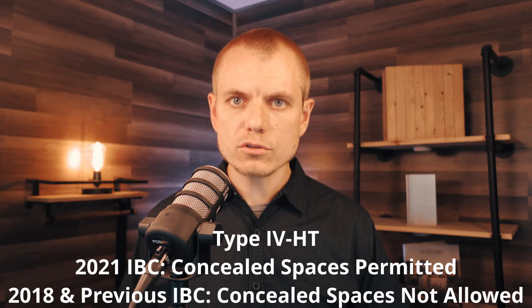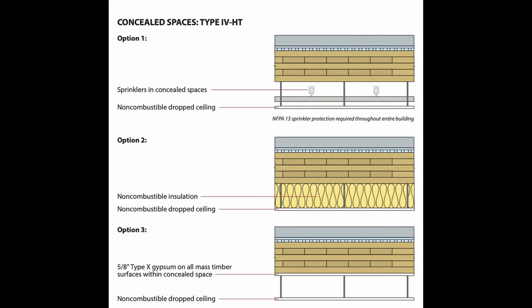Within the 2021 IBC, Type 4HT projects now permit concealed spaces — previously, concealed spaces were prohibited in Type 4 construction (now renamed 4HT). The 2021 IBC gives three prescriptive options: first, sprinkler the concealed space; second, fill it with non-combustible insulation; third, protect all mass timber surfaces within that concealed space with a layer of 5/8" Type X gypsum wallboard. This works well for a drop ceiling below a mass timber floor panel.